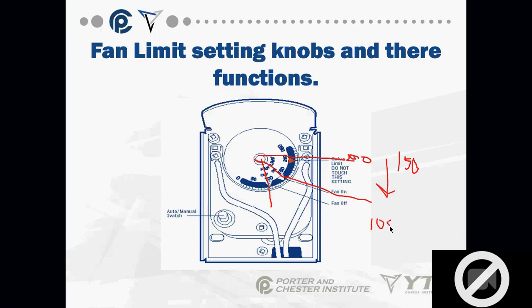These are normal settings. These are the factory default settings. Okay, fan on, around 150 degrees. Fan off, around 100 degrees. High limit, 200 degrees. These settings tend to work pretty well. Okay, why do I want to turn the fan off at 100 degrees and not bring that temperature down lower? Because it's going to keep rising. It won't keep rising because there's no burner at this point. This is the off cycle. But someone else said something, so go ahead and say that again. I didn't hear it. You always want the temperature to be higher than your body temperature. Correct. I always want the temperature of the air I'm blowing out of the ductwork, unless it's air conditioning, to be hotter than my body temperature. I don't want the building occupants to feel cold drafts. Okay, so I turn it off at 100 degrees.